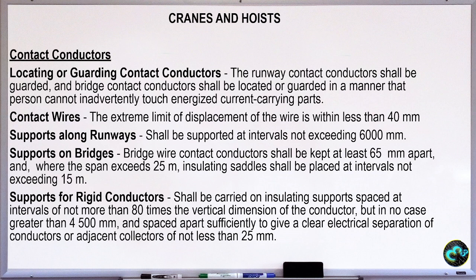no? Okay, then support on bridges, so the conductor shall be kept at least 65 mm apart, so that is in case na magkaroon ng interference, may isang conductor na madikit tapos the insulation will be damaged, so at least pag malayo, so hindi magkakaroon ng arcing. Then within the span that exceeds 25 m, tapos insulating saddle shall be placed at intervals not exceeding 15 m.